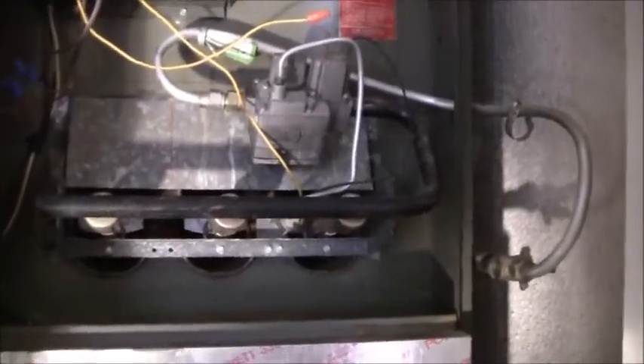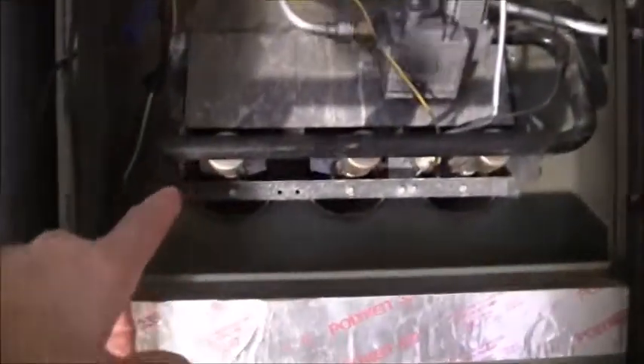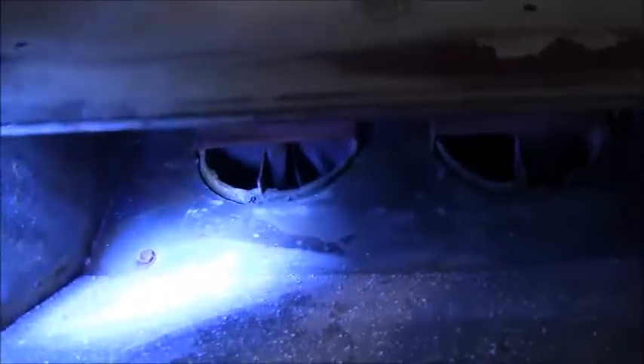The way that the draft works, this is just an 80% furnace, so there's no inducer draft fan motor. So basically your combustion air is going to go in here, and then your products of combustion are going to come out. Let me get the flashlight. They are going to come out these tubes right there, and then they're going to go up. I'll show you where they go up. They go up right there at the top, okay?